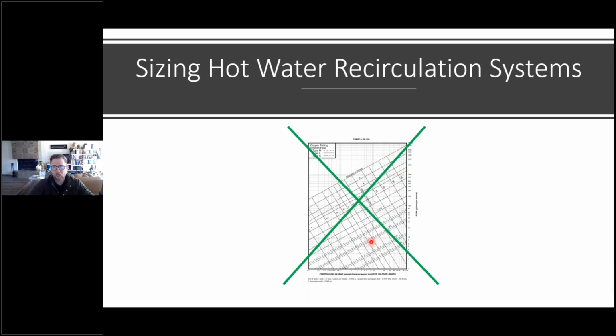Now, let's talk about the equations governing this. First off, we need to do a little bit of a process of elimination of which equations we shouldn't use. One of the errors that many young designers make is they will base all their flow off of velocity. This is the chart for copper tubing based on the Hazen-Williams equation, which we'll touch on later. But if you just go based off velocity, you'll notice that there's friction, pressure drop per 100 lineal feet on the bottom here, and then flow on the y-axis.